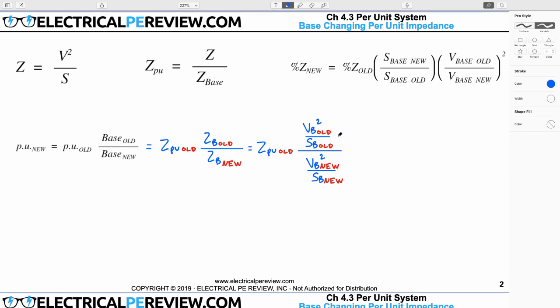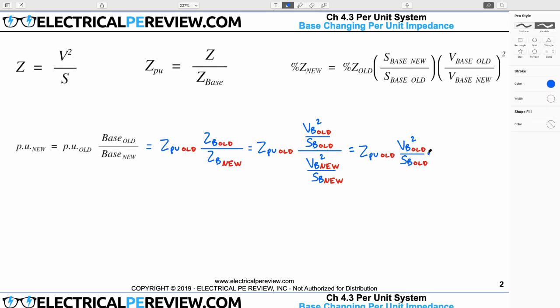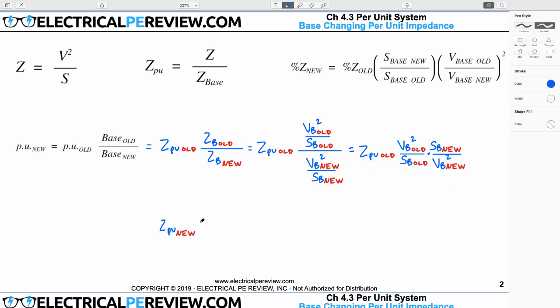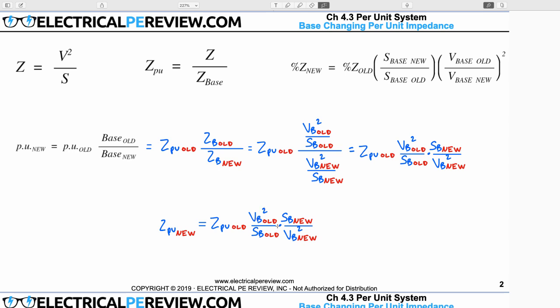This is a little complicated — how do we get rid of this? Anytime I have a fraction over a fraction, I can move the bottom fraction to the top by swapping the two terms: move the denominator to the numerator and the numerator to the denominator. So we keep our old per unit impedance unchanged, keep our old base impedance expressed as V_B_old squared over S_B_old, and then bring the bottom fraction up — meaning our new power base goes to the numerator and our new voltage base squared goes to the denominator. Now we have: new per unit impedance equals old per unit impedance times old voltage base squared over old power base times new power base over new voltage base squared.